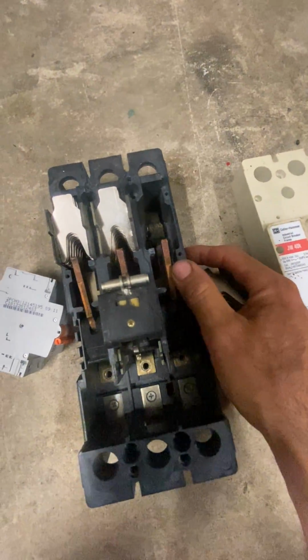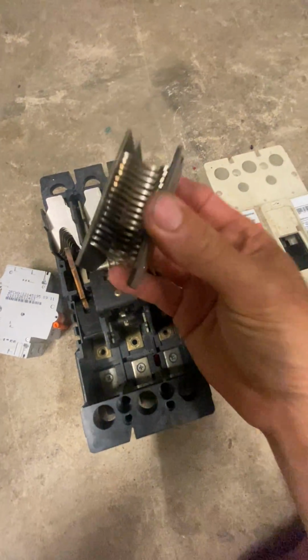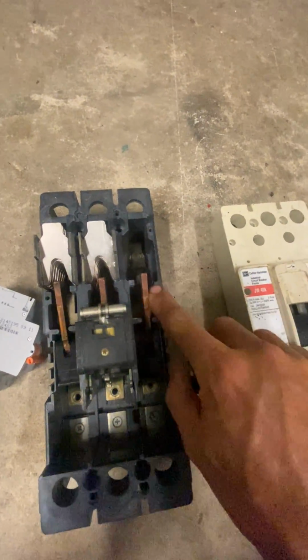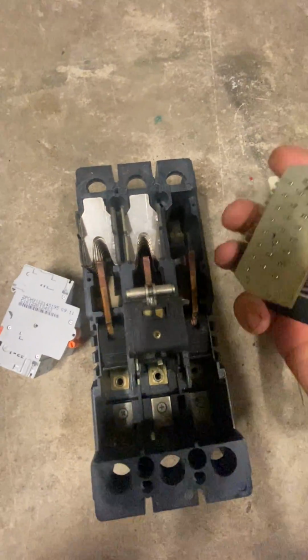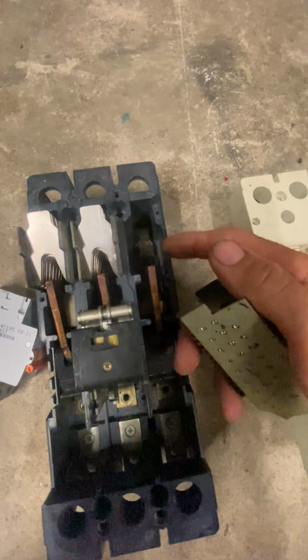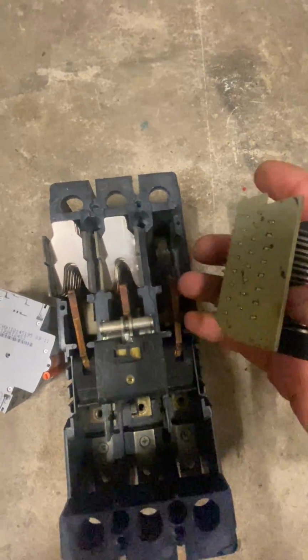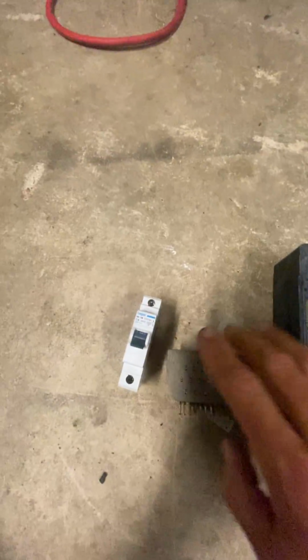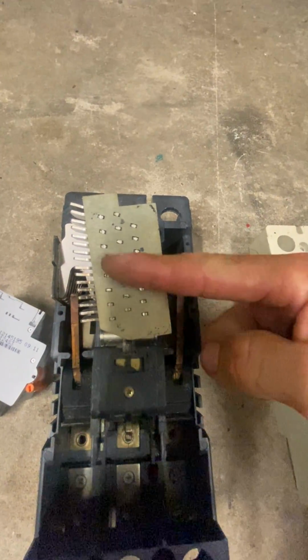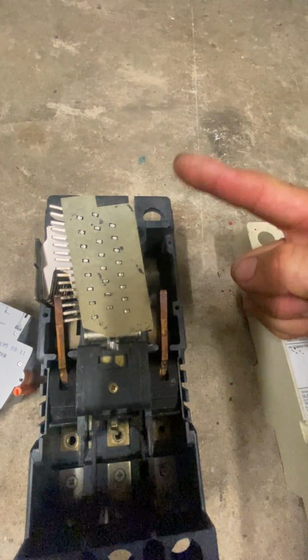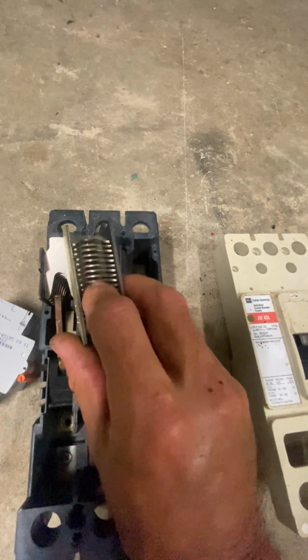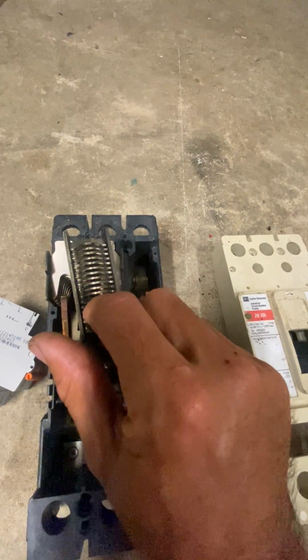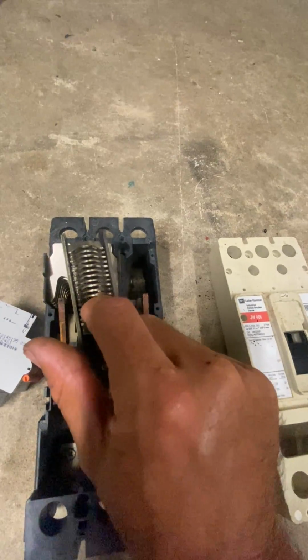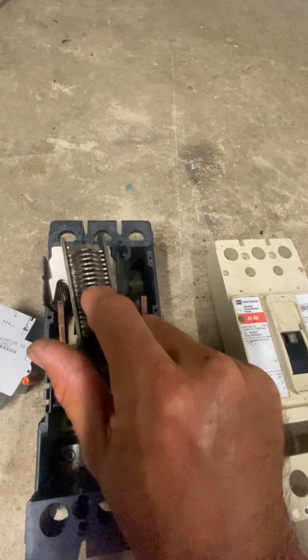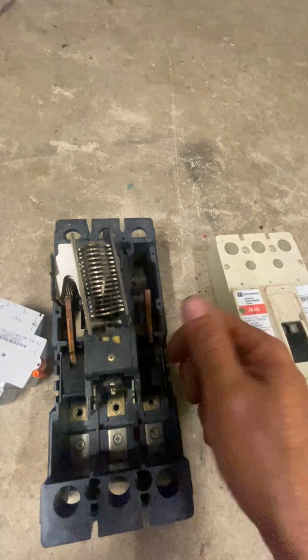So this is what these are for: when under a fault condition this trips and these arms come back, an arc will be formed, a spark or flash will come across as it breaks. As you can see with the angles there, it's in an arc, it's in a curve. As the arm comes through, it will flare the arc, and then these chutes will just cut through the arc, and the arc will basically lose energy as it opens up. So you'll lose a little bit through each one, and then as it opens up, the arc will be basically broken in that.